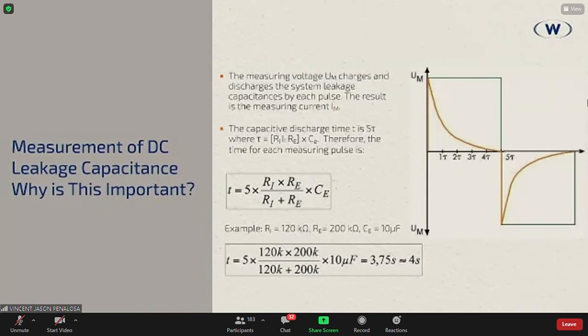Now, when you look at this, I have a little bit of a formula here. Of course, you guys don't have to do this. Your system will do it for you. But we need to understand how much capacitance we have in the system. Why? It will actually influence the length of time before an insulation monitoring device can actually give you a measurement, right? According to the IEC, an insulation monitoring device should be able to give you a measurement in 30 minutes for high leakage capacitance systems. 30 minutes, ang tagal nun. But just because of leakage capacitance, it really does take time. And there have been instances where poorly built insulation monitoring devices failed to give a measurement at all. So you have a little bit of a formula here. As you can see, the higher the leakage capacitance, the longer the time, right?